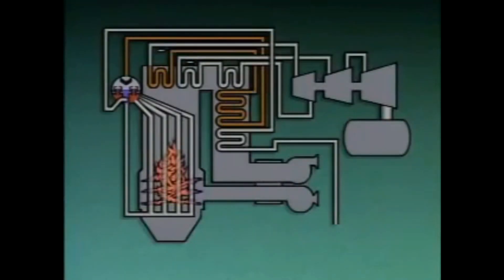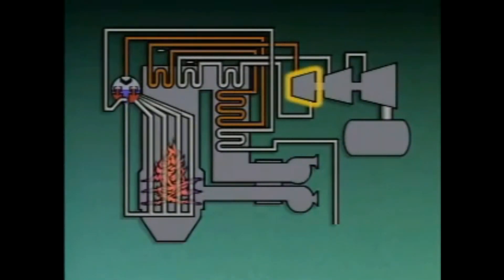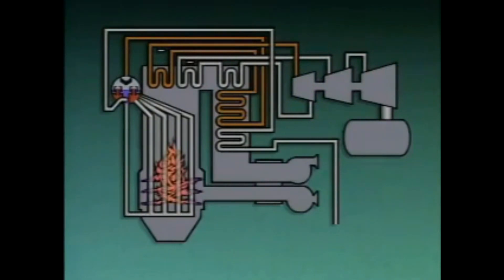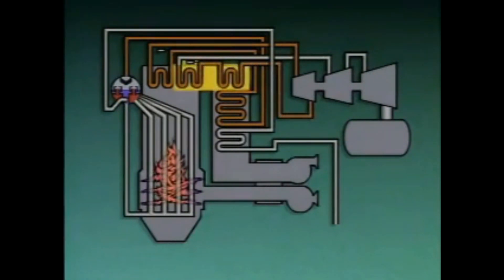From the secondary superheater, the steam goes to the high-pressure, or HP, section of the turbine. As the steam flows through the HP section, it gives up a lot of its energy and its temperature and pressure drop. Before it moves on to the other sections of the turbine, the steam returns to the boiler, where its temperature is increased as it flows through one or more reheaters.